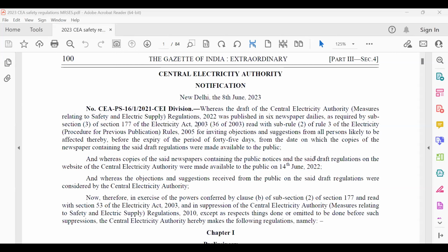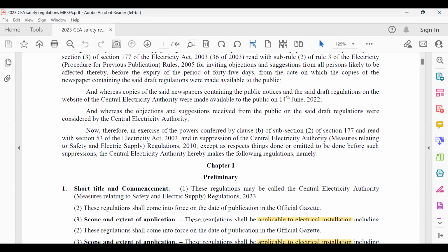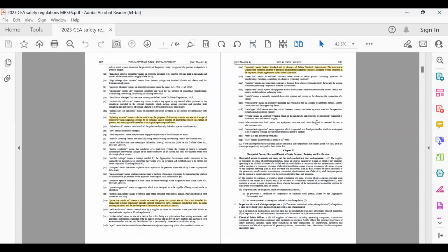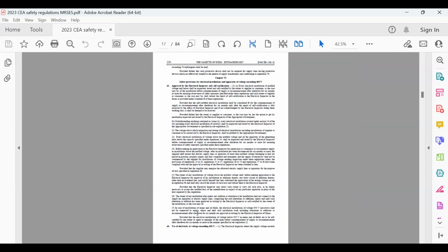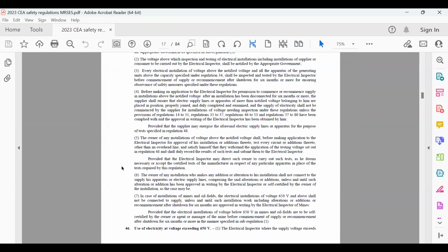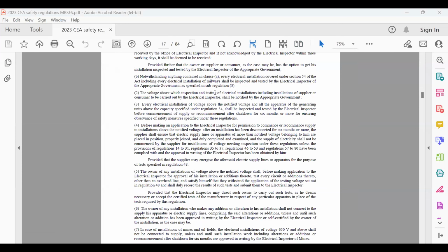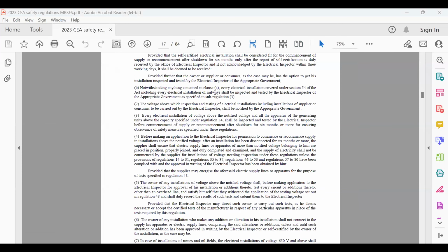Thank you. Appav sir, what is your opinion on this? Are these meters, generally insisted for the electrical contractor, sufficient enough to carry out a verification? Yes, sir. I have already mentioned under regulation 45.5, the consumer should submit the application, and with that, test every circuit. This means the consumer has to rely on the contractor, who in turn relies on the instruments. So what the NEC and IS 732 verification process requires - earth loop impedance and so many other parameters - many instruments are yet to be prescribed.